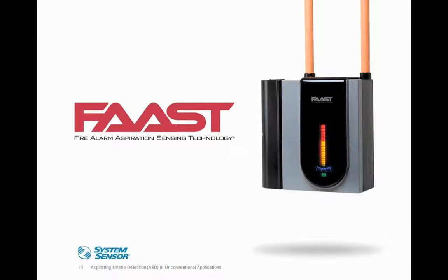They're currently using a beam detector or beam detectors, and they're getting some false alarms when the doors open, dust blows up, or morning fog rolls in. Must be maybe a coastal area. Would FAAST be a better use in that application?